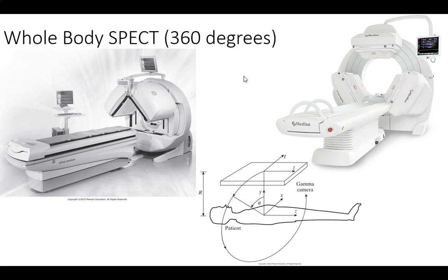So from the front, the only thing competing from the sides and everything is your lungs, and that's just air, so that's really not making much of a difference, right? So the quality of image you get from a SPECT system out the front is way better than the one out the back if you're doing a heart scan. So if you're specifically targeting one special organ and you include the stuff from the back, you actually worsen your image.